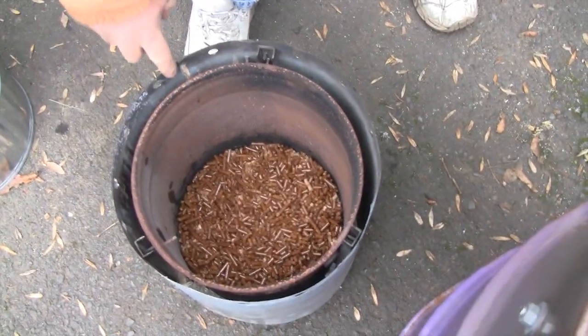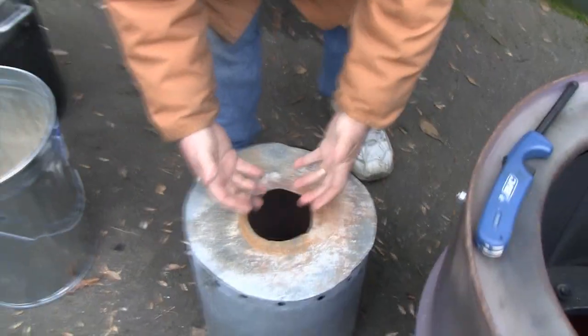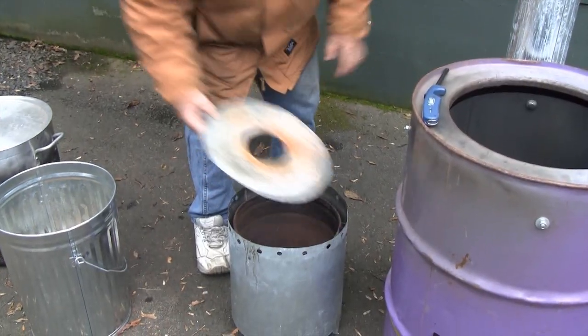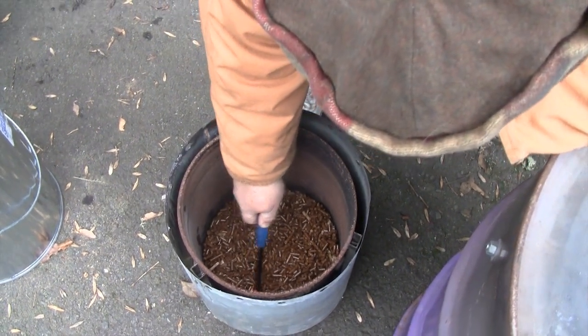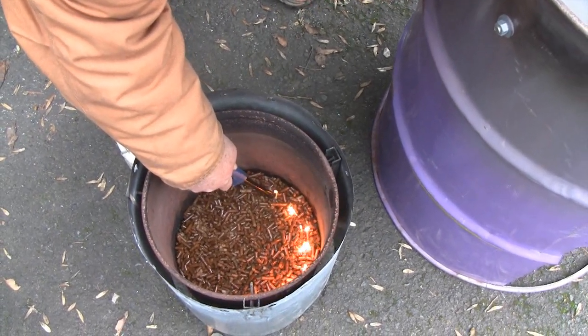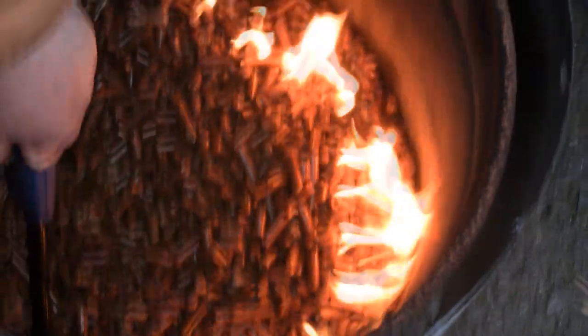You can see that the air comes up this gap, and then we put a cover over so that the air is flowing up. It flows underneath the cover and then comes up through the top. Because this hole is all filled with flame, you have very clean combustion. All the gases have to pass through flame, which means very clean combustion.